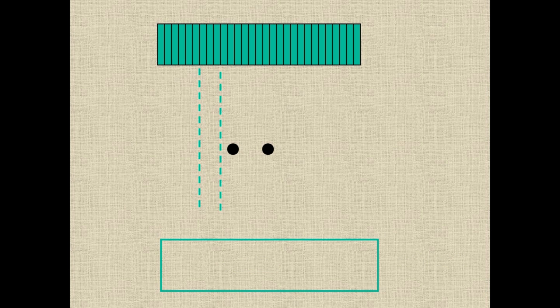If we narrow the beam width, we can then have a period of time where the beam interacts with one reflector, there's a gap between the two with no reflections coming back, it interacts with the second reflector, and then moves on. This is different because the end result now will be that the ultrasound machine can differentiate between these two different reflectors at the same vertical distance from the probe.